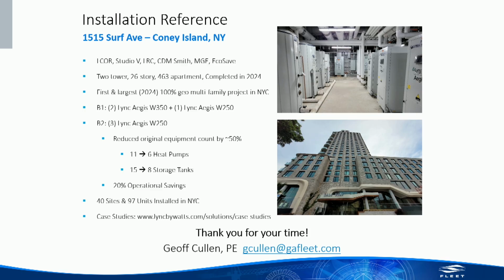We were able to actually come in and reduce the amount of equipment due to the use of CO2, as well as increase the overall efficiency, because of the higher COPs than the unit that was originally designed. Because we were able to exceed that 15 horsepower capacity, we were able to go from 11 heat pumps down to 6, and from 15 tanks down to 8, using about half the amount of storage. Then paired with the better efficiency of the equipment, we were able to save operationally 20% year over year. So a great case study for the use of CO2 heat pumps specifically for domestic hot water and geothermal.